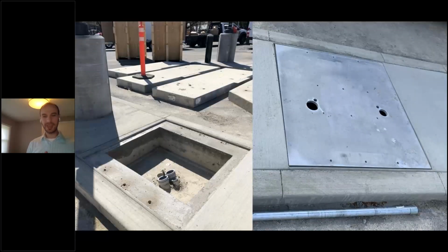Here's what we've done. We've actually cast in place a void into the concrete, or really a vault, and installed a metal lid on top of it. If you're thinking about which dispensers or charging stations to install at your fueling islands and want flexibility, maybe starting with one brand today and wanting the option to change to another later, this helps. If we want to change the type of dispenser installed in the charging island, all we have to do is go to a metal fabricator and have a new plate made that matches the bolt pattern required to mount the equipment onto this pad, and also enables the conduit to come up wherever a manufacturer might require. This makes it easy to have flexibility and choice, or even to begin your design process before you know exactly what you want for your charging equipment and dispensers.